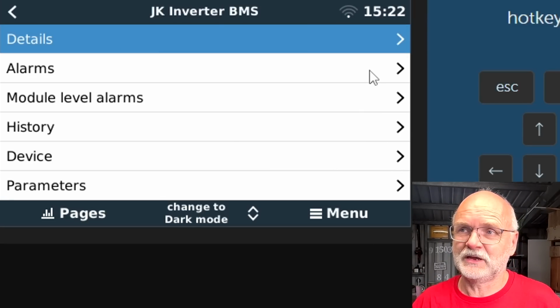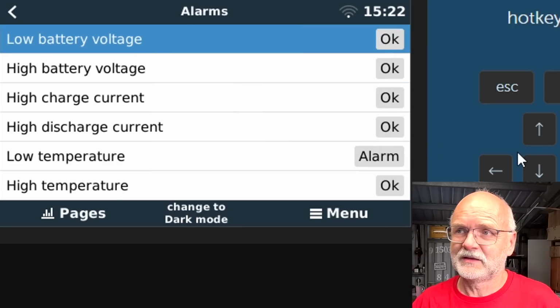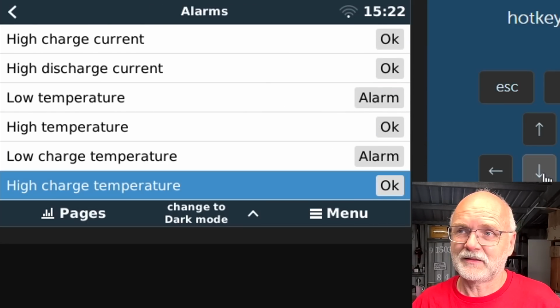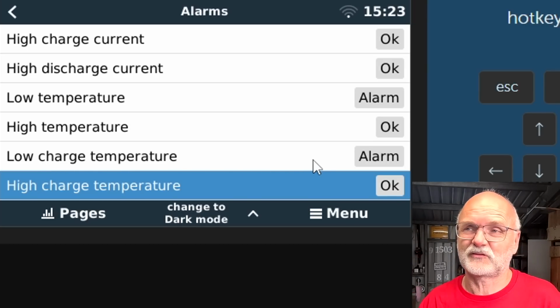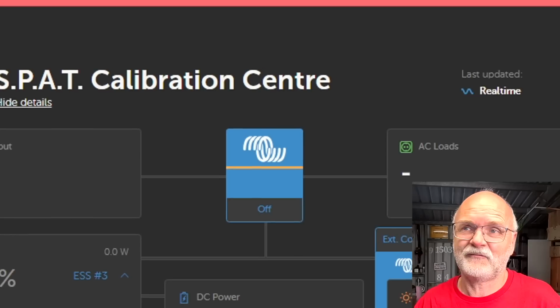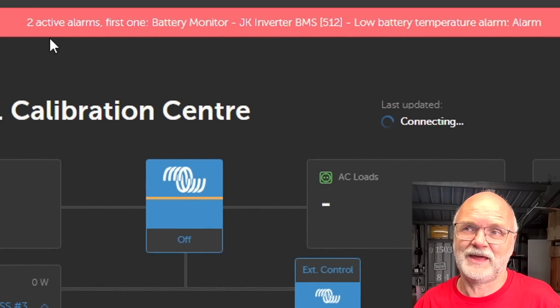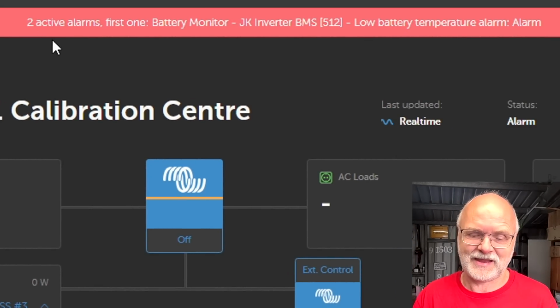And if we have a look here in the alarm settings, we can see we've got a low temperature alarm and we've got a low charge temperature alarm as well. This is just how the BMS reports this to the Victron system, and hence we have 2 alarms here in the Victron VRM, but it's only an under temperature protection. So this all works fine if there's only one battery connected. If you have more than one, it doesn't work anymore. At least it doesn't tell you there's an alarm.